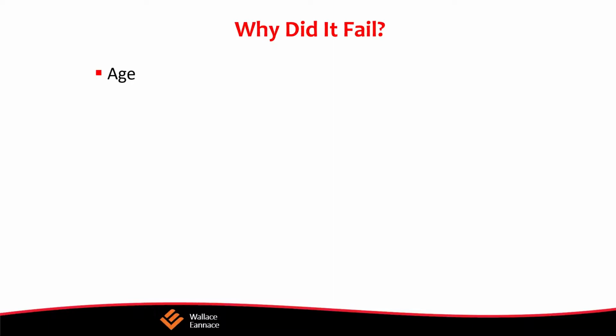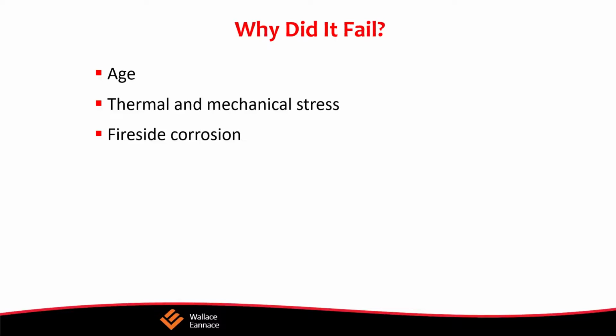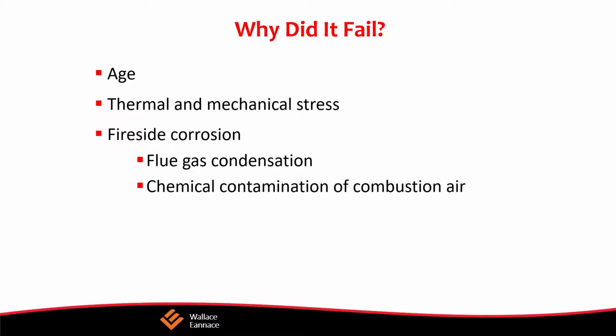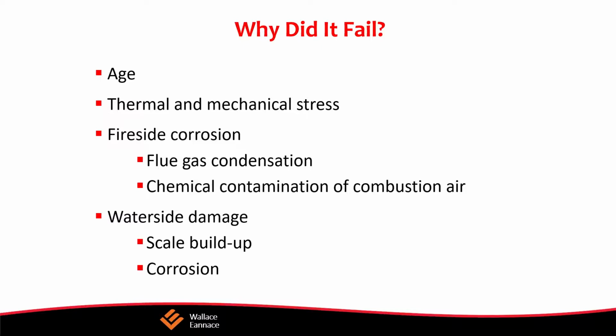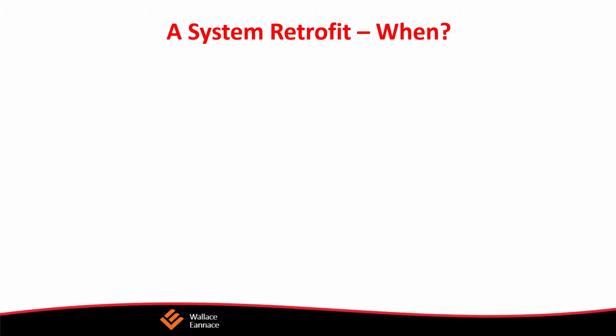And then why do these boilers fail? Well, a lot of them just get old. You have thermal stresses and mechanical stresses. Every time you heat something, the metals expand. As they cool down, they contract. Over time, it'll cause wear, small fractures, and eventually destroy or break down the metals. You can have corrosion that is caused from chemicals, either flue gas condensation or chemical contamination of the combustion air. And then on the water side, very common is scale buildup and corrosion. Anybody who's taken out a boiler will see that.